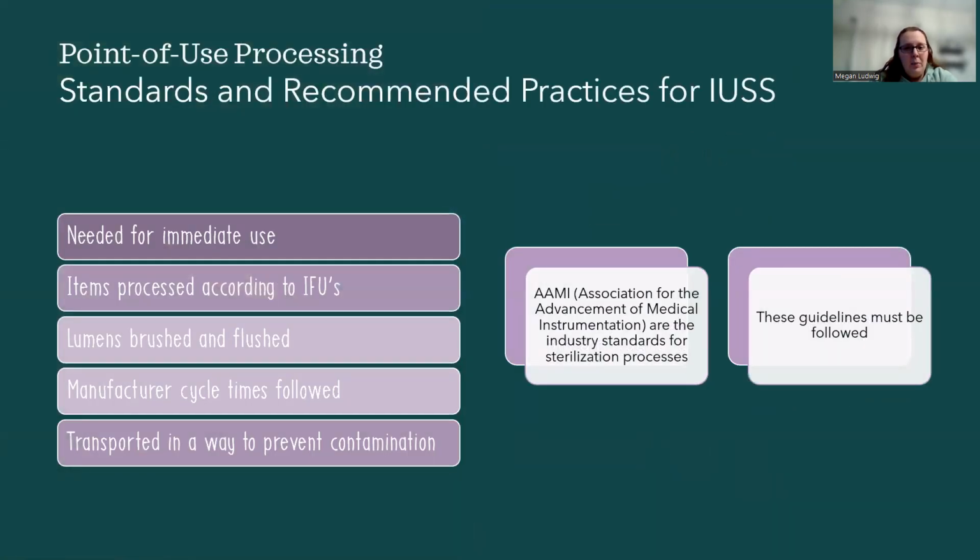So if we're talking about immediate use steam sterilization, what are those recommendations? Okay, for obviously immediate use. It's not for the next patient. It's for the patient that you're using it on. Okay. You have to be careful with what you put in an immediate use steam sterilizer.